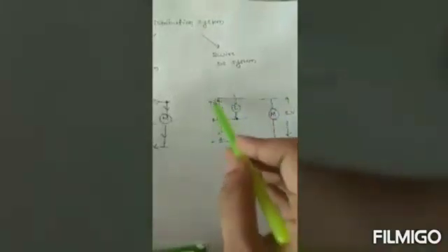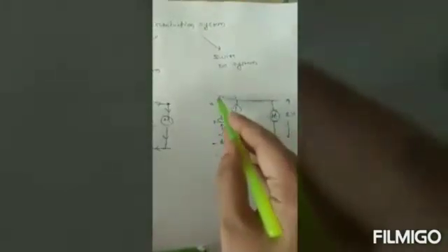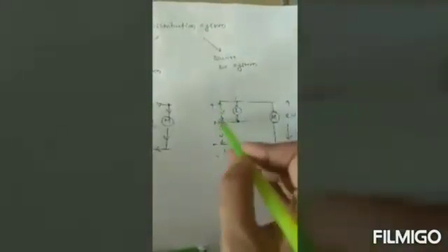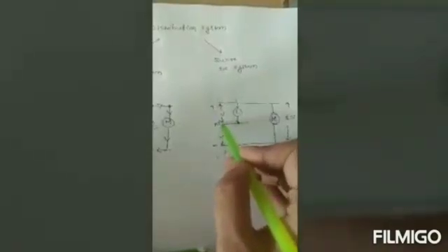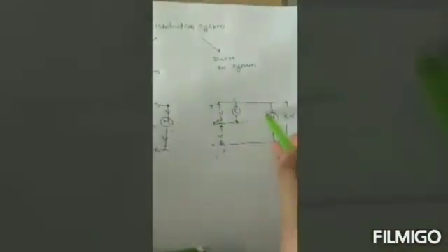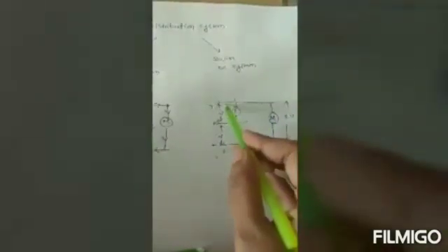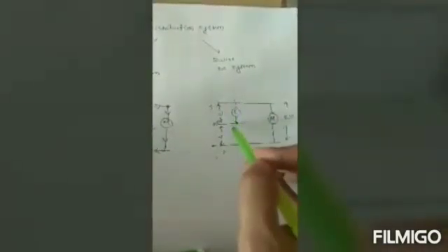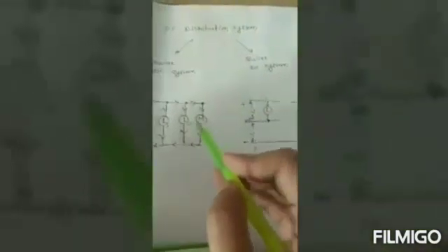In this three-wire DC system, we can see the three wires, that is the first wire, the second, and between them the neutral wire, where the voltage between the two outer wires is twice the voltage between an outer and the neutral. This is the whole phenomenon of the distribution system of the two-wire and three-wire systems.